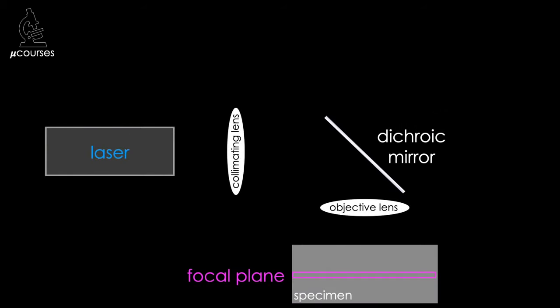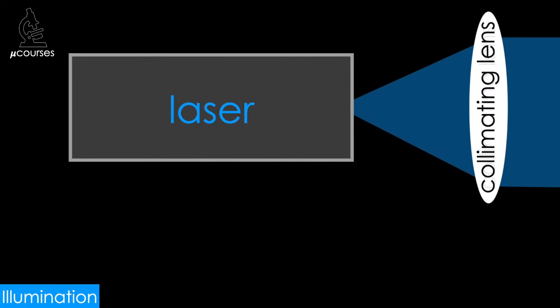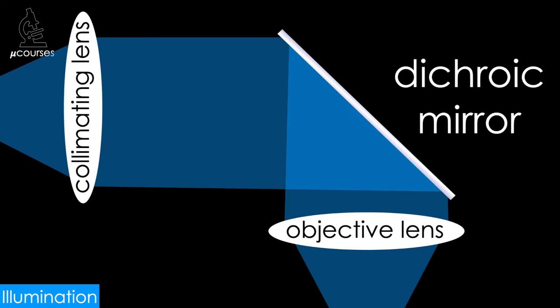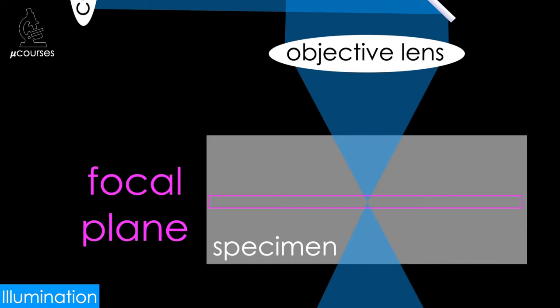Let's look at a diagram of a simplified confocal microscope to see how focused illumination can be achieved, looking first at just the illumination light path. In confocal microscopes, lasers are most commonly used as a source of photons to illuminate the sample. The light from the laser passes through a collimating lens, which forms a beam in which all the light waves are traveling in the same direction. The light is then reflected by a dichroic mirror to the objective lens, which focuses the collimated beam into a point source at the focal plane. For more on how lenses form collimated beams or focus light, check out the microscope alignment for optimal image quality microcourse.